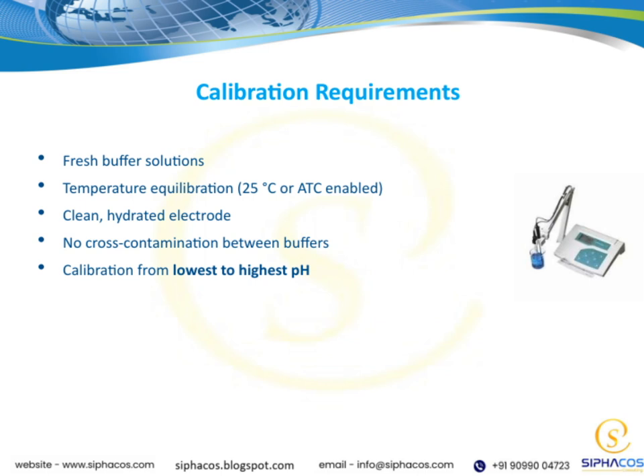Also, ensure your electrode is clean and properly hydrated before calibration. A clean, moist electrode provides consistent and accurate responses. Equally important is avoiding cross-contamination between buffers. Using fresh buffers for each calibration step prevents contamination that could skew your results.